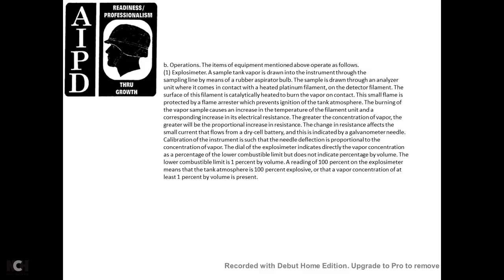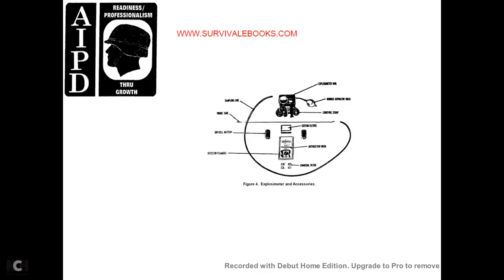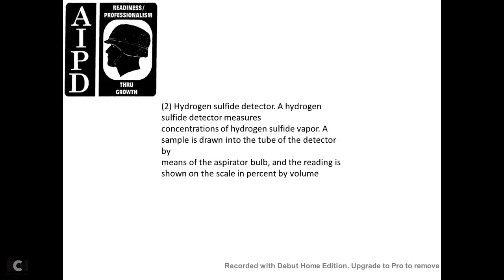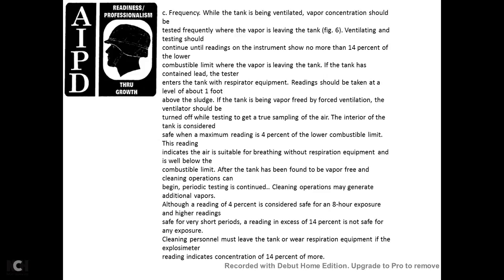A reading of 100% on the explosimeter means the tank atmosphere is 100% of the lower explosive limit, indicating at least 1% vapor by volume is present. Figure 4 shows explosion meters, sampling line, and accessories. Figure 5 shows the hydrogen sulfide detector — a glass detector tube inserted in a frame. The reading is shown as a percentage on a scale; the aspirator bulb is squeezed 10 times to draw a sample into the tube. The sample is drawn through the detector tube by means of an aspirator bulb, and the reading is shown as a percentage by volume. While the tank is being ventilated, the vapor concentration should be tested frequently. Ventilation and testing should continue until instrument readings show no more than 14% of the lower combustible limit.